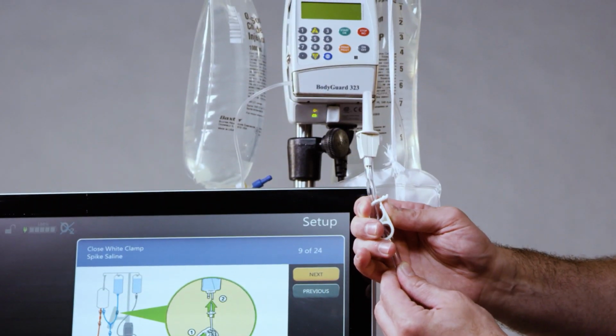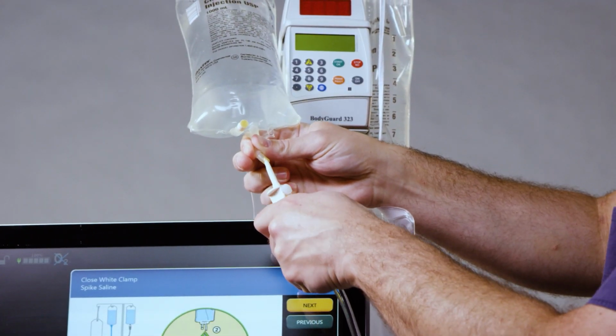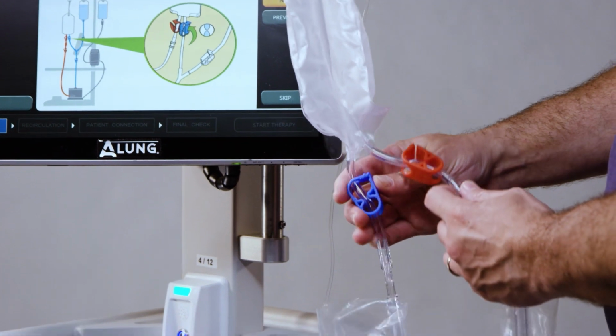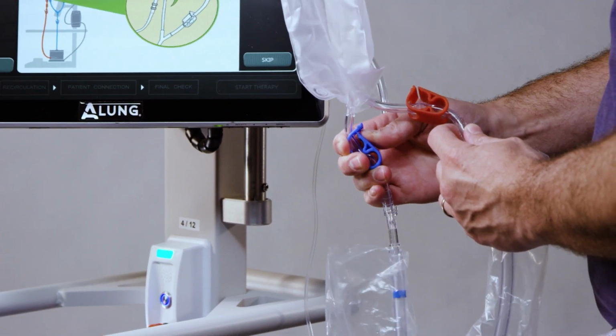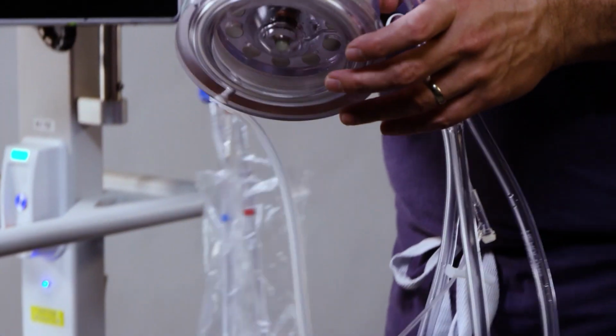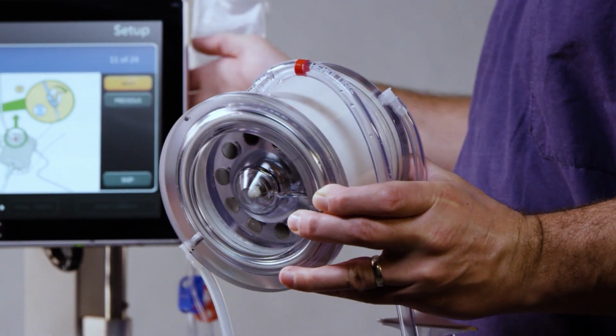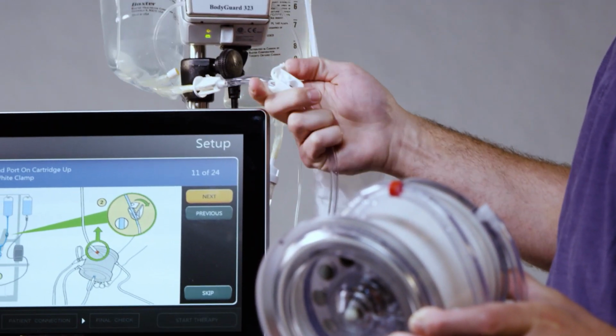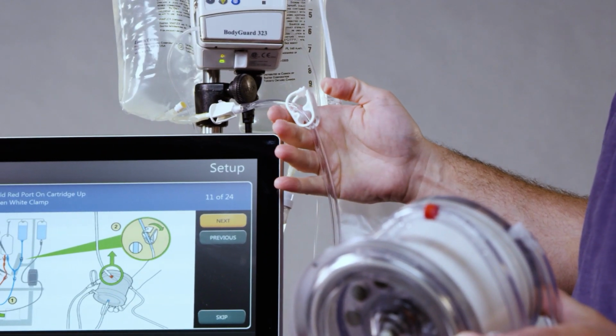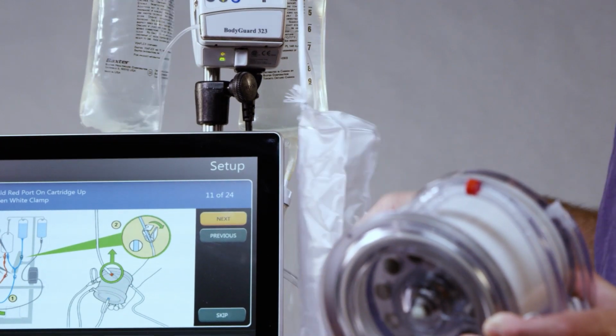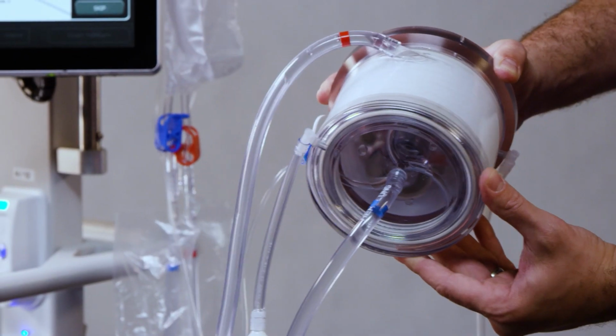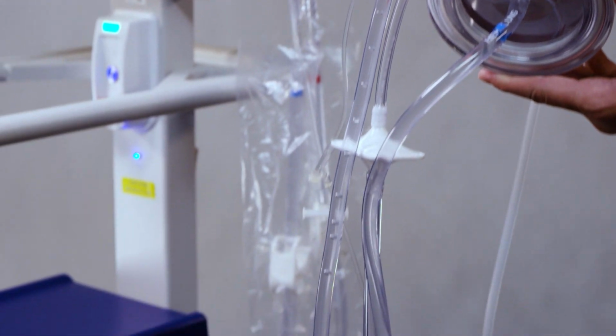Close the white clamp near the priming spike on the blue tube, and then spike the priming solution. Next, close the blue clamp on the recirculation bag. Prime the cartridge by holding it upside down with the red outlet facing up. Open the white clamp near the priming spike to start the flow of saline into the circuit. Gravity will flow saline through the tubing and the cartridge.